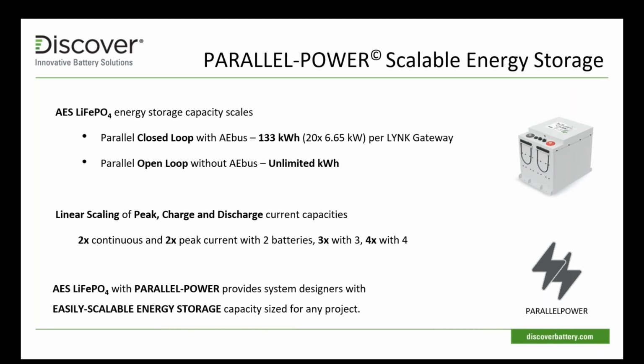So to recap, we can do what we call a closed loop system, requiring a LYNK gateway. We can put about 20 batteries on that, reaching about 133 kilowatt hours. That 20 number can be extended a little bit. There, it's really about how much data is being transferred around rather than the power. As you can see, if we do an open loop without the communications to the inverter, the kilowatts are unlimited. It's really just like a lead-acid system. So we're going to get into a little bit of detail on closed loop and open loop, as this is an important understanding.